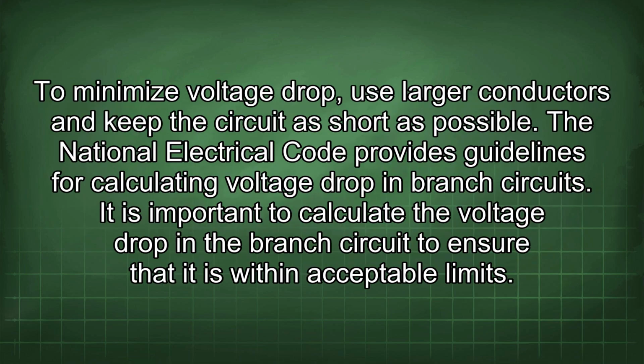To minimize voltage drop, use larger conductors and keep the circuit as short as possible. The National Electrical Code provides guidelines for calculating voltage drop in branch circuits. It is important to calculate the voltage drop in the branch circuit to ensure that it is within acceptable limits.